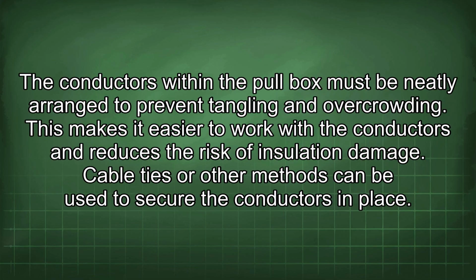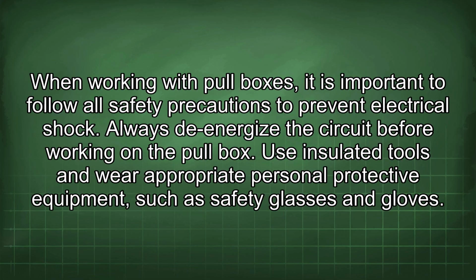The conductors within the pull box must be neatly arranged to prevent tangling and overcrowding. This makes it easier to work with the conductors and reduces the risk of insulation damage. Cable ties or other methods can be used to secure the conductors in place. When working with pull boxes, it is important to follow all safety precautions to prevent electrical shock. Always de-energize the circuit before working on the pull box. Use insulated tools and wear appropriate personal protective equipment, such as safety glasses and gloves.